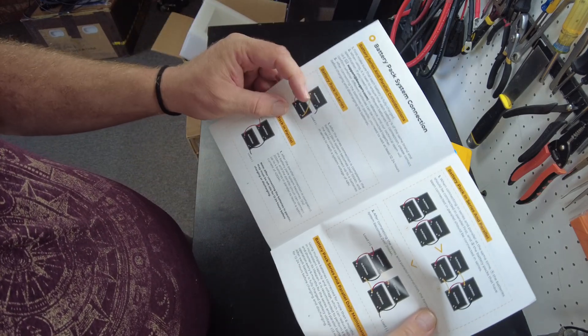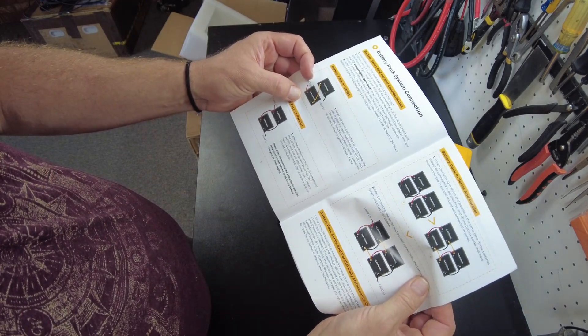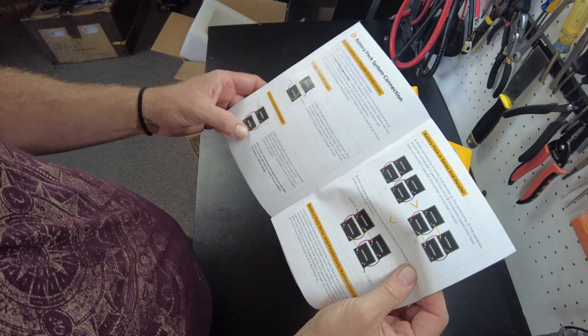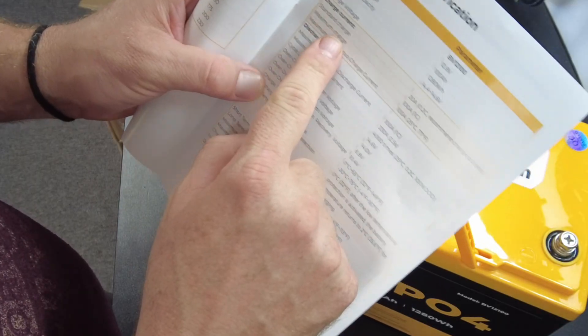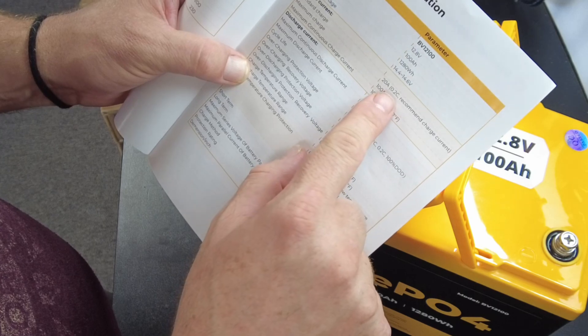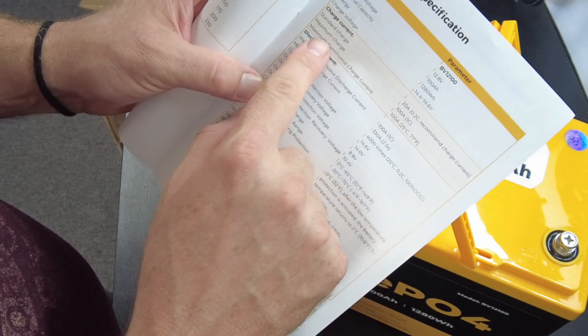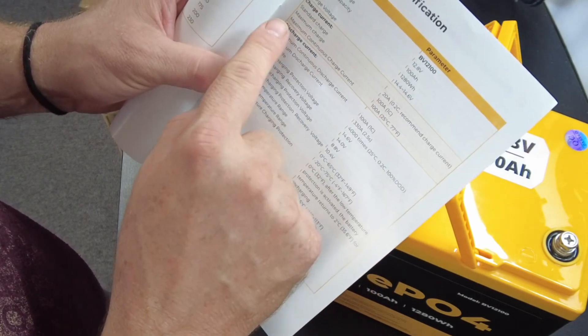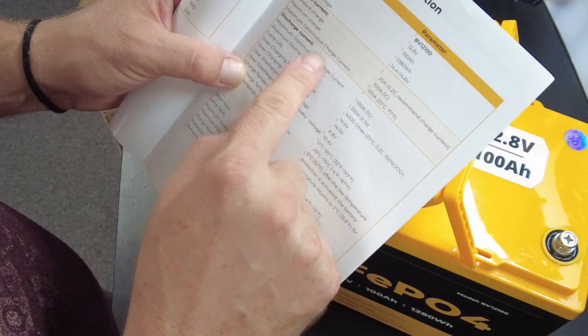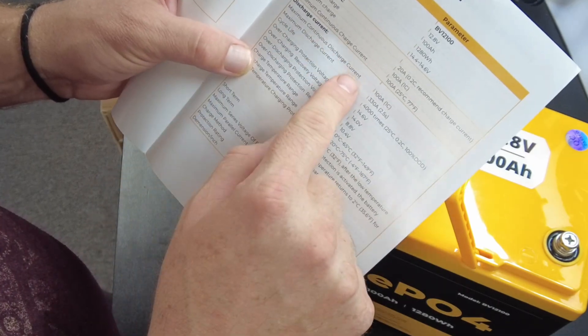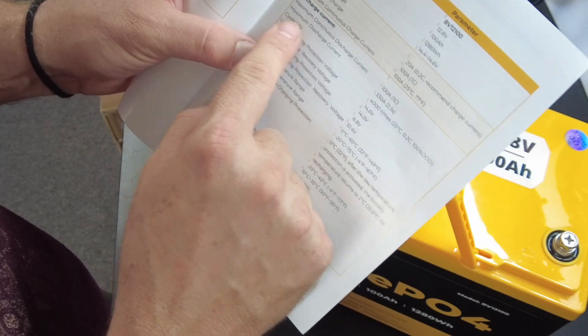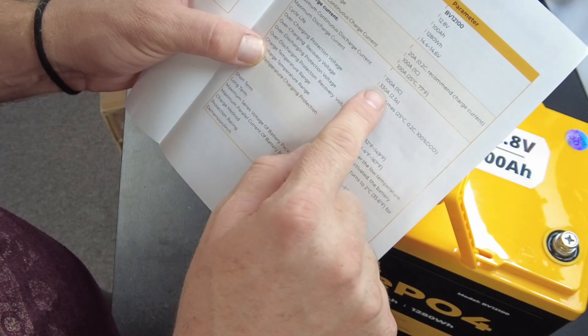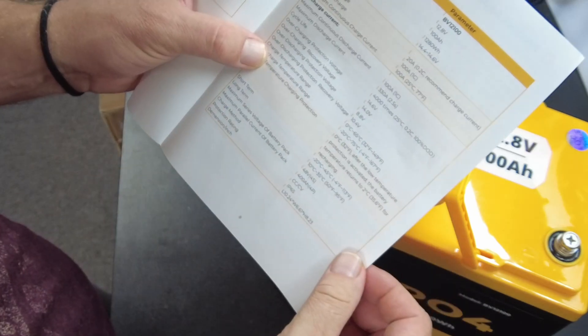The manual says you can put 4 in series and you can connect 4 in parallel. The standard charge current is 20 amps, 0.2C recommended charge current. The maximum charge is 100 amps. The maximum continuous charge is 100 amps. The maximum continuous discharge is 100 amps. And the maximum discharge current is 330 amps for 2.5 seconds.